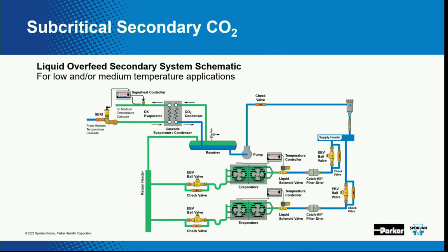I don't like it saying liquid solenoid, it's actually acting as a pulse valve - that valve is clicking, click, click, click, maintaining superheat, and that's how you're getting that expansion at that evaporator. If it's sized properly, I don't think the lines are acting like a pulse valve - it's on/off, but we have a pulse valve and that's clicking.